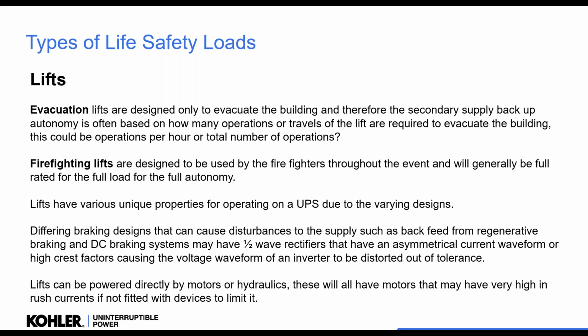But then we have a firefighting lift that is used throughout the event. So typically that is fully rated for the full autonomy of the event that we need to cover, 1 hour, 2 hour, 3 hour. And we need to understand fully how those lifts are supplied. Do they have a soft start? Do they have regenerative braking? Do they have DC braking? Because that will affect the type of UPS that we use to feed it.